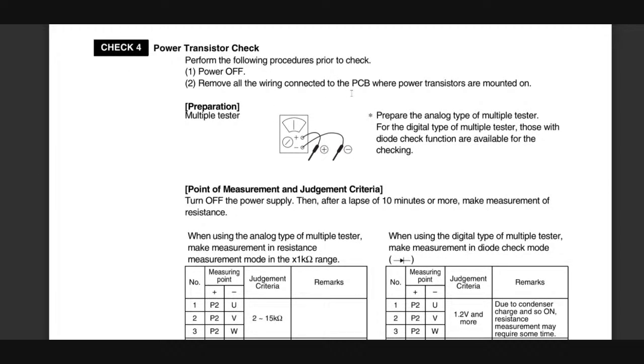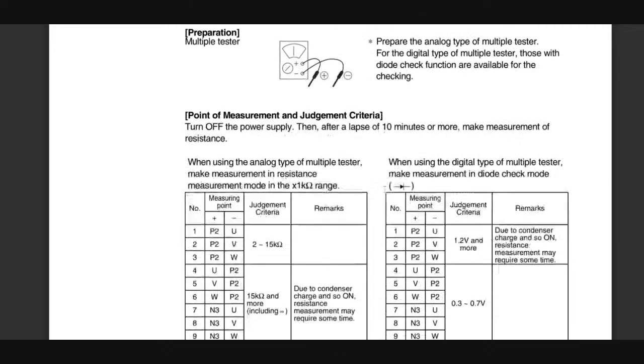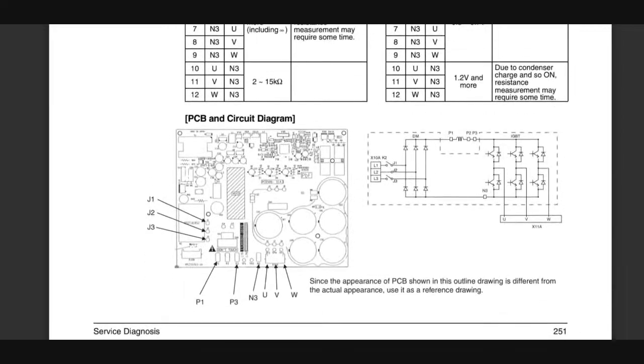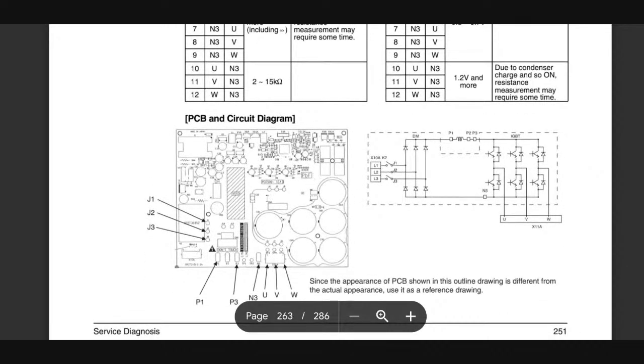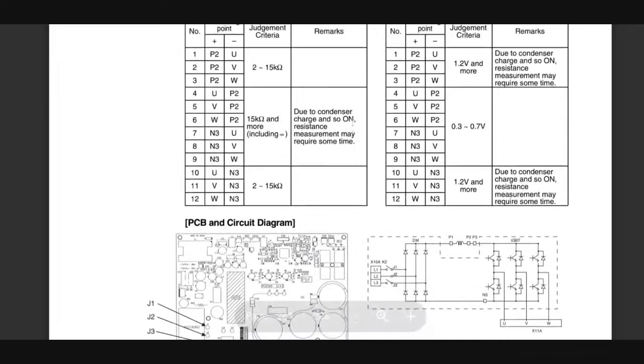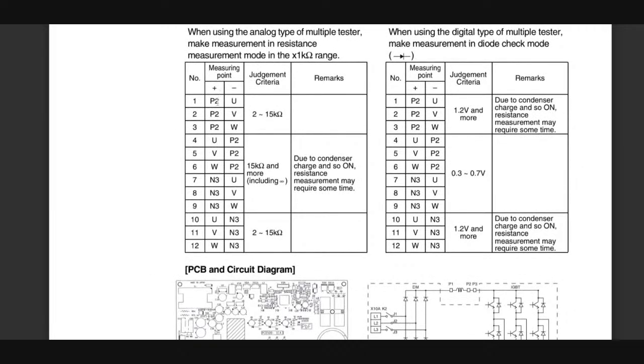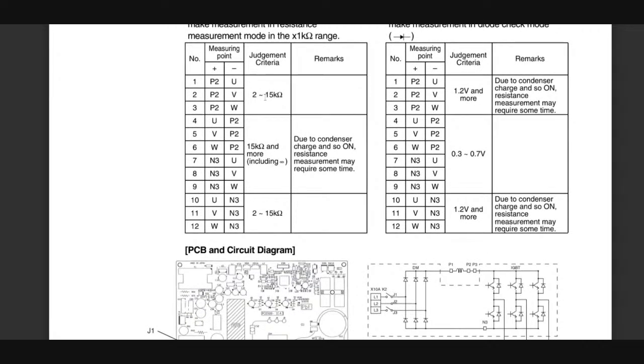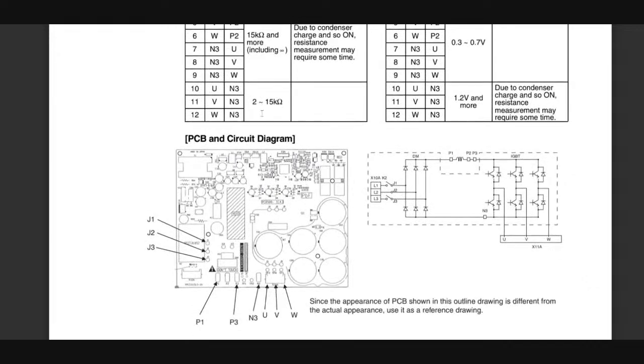This is a service procedure. We're going to power off, remove all wiring from the PCB. You've got your meter, and this is our inverter circuit. So these are our inputs, our outputs. The UVW should be going to the compressor. We have our power in. It's going to tell you that between all these different points, so between P2 and U, you should have this ohm value, 2,000 to 15,000.